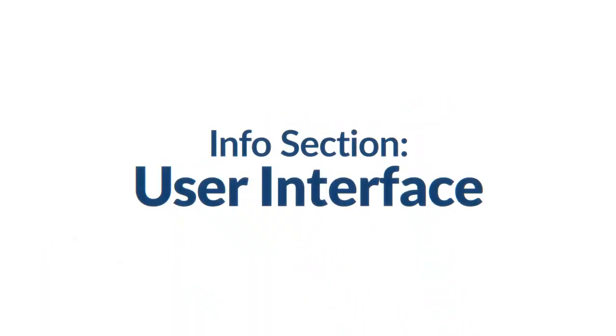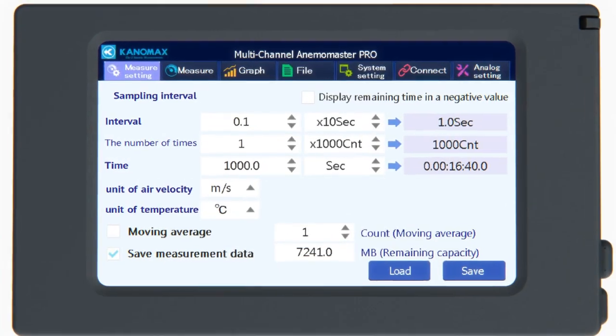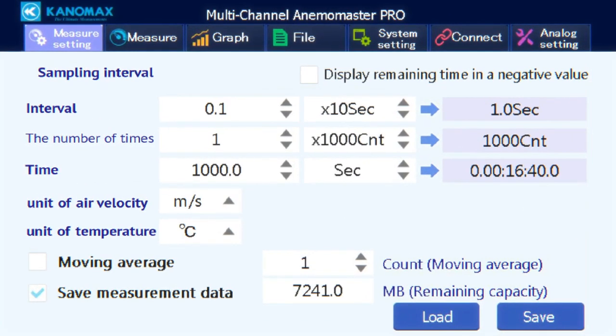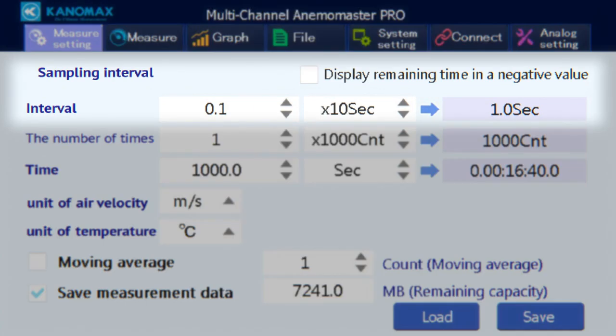For the rest of the video, we'll go through the menus of the 1590 in depth. On the measure settings screen, there are a number of ways to customize your measurement. Interval or sampling interval is where you set how long it takes for your sampling to update. You can choose a duration between 0.1 and 6,553.5 seconds. The box next to that is for selecting the unit of your sampling interval. You can choose between 1 second, 10 seconds, 100 seconds, and 1,000 seconds. The interval of your sampling will be calculated and shown in the box to the right.